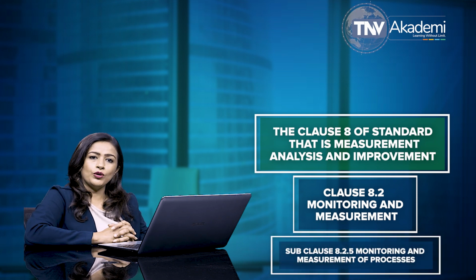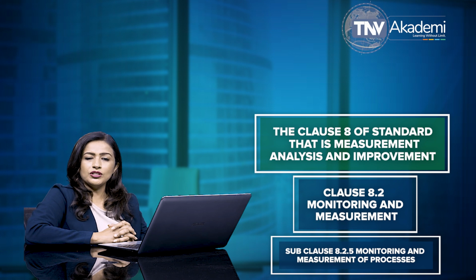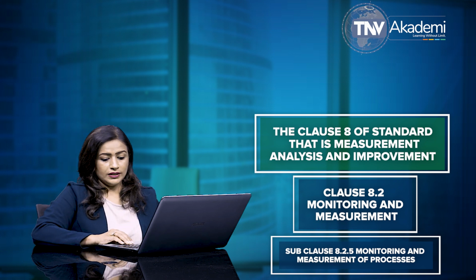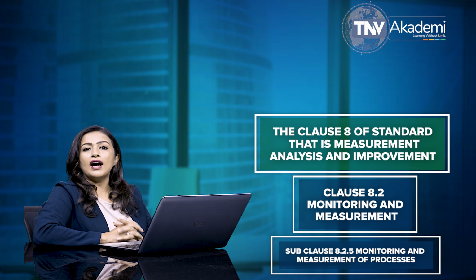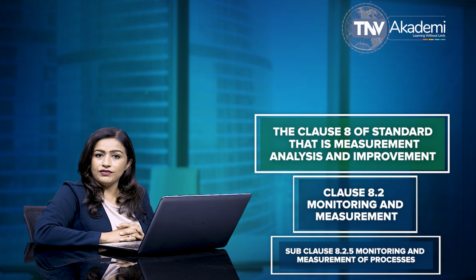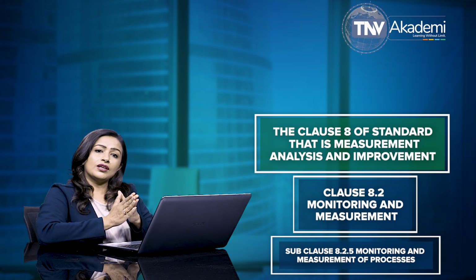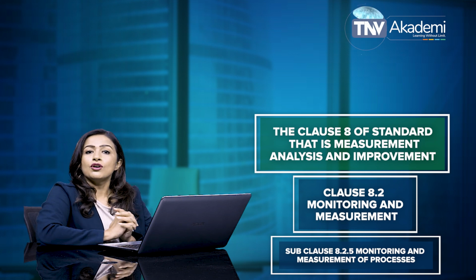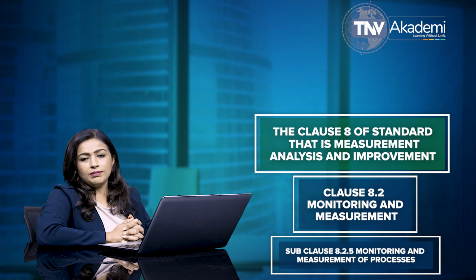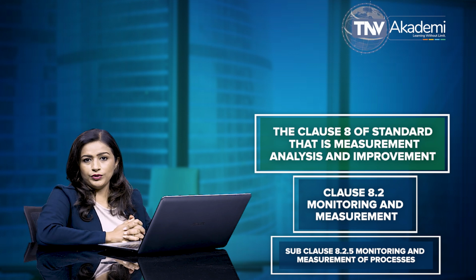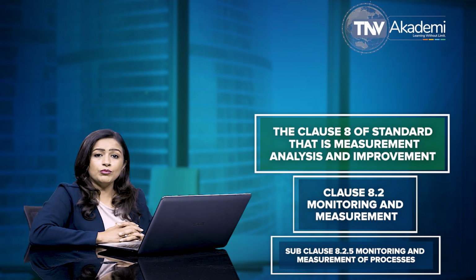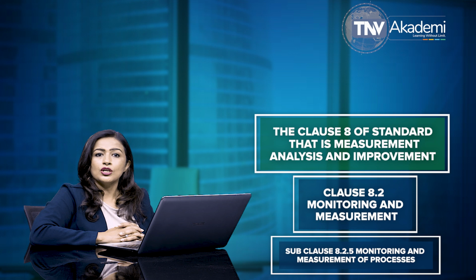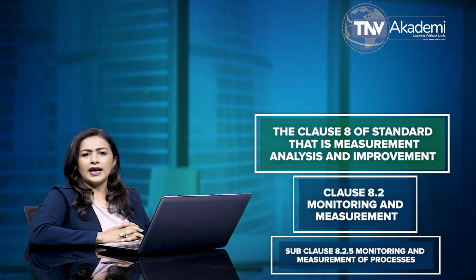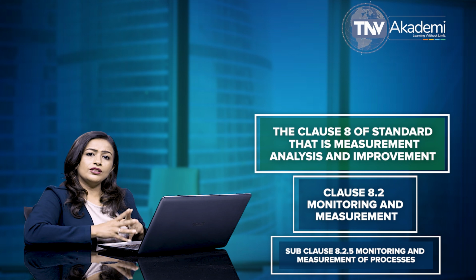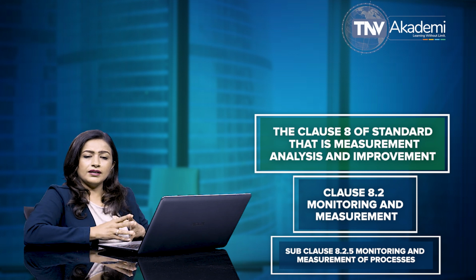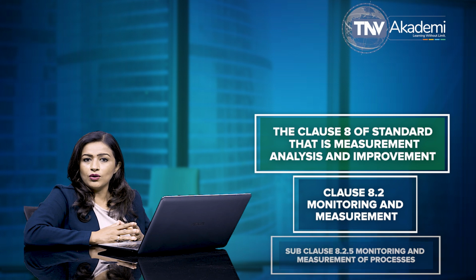Coming to the subclause 8.2.5, monitoring and measurement of processes. This subclause 8.2.5 of ISO 13485 states that the organization is required to apply suitable methods for monitoring and measurement of the quality management system processes as appropriate. These methods must demonstrate the ability of the processes to achieve planned results. As per clause, organization is required to take appropriate correction and corrective actions when planned results are not achieved.